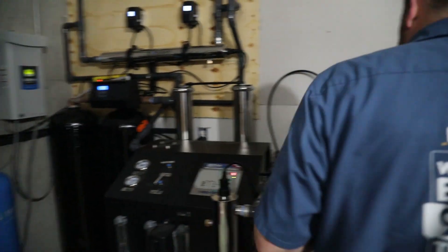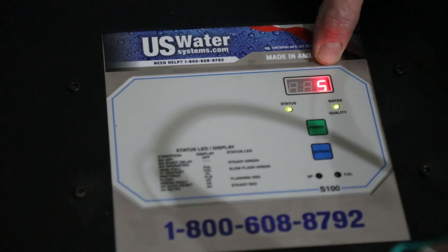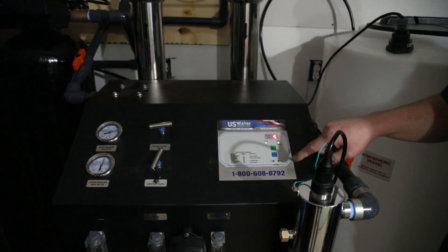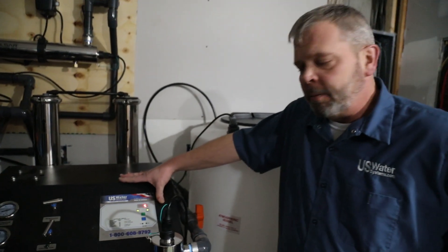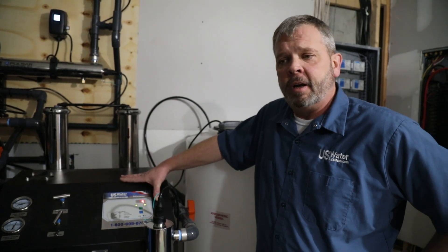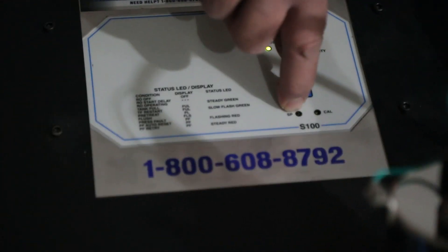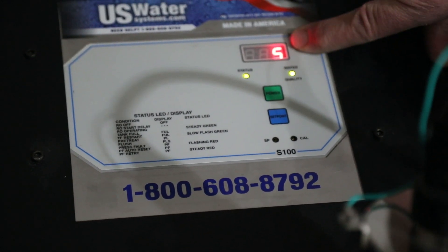Now we're actually putting clean water into the storage tank. You can look at the screen here — we went from like 494 TDS down to high rejection, so we're cleaning really well at this point and the water quality is good. You have the ability to change where you want the water quality light to turn on. We put it from the factory at 100, because depending on how bad your water is, 100 may be the best that you can get. Anything over 100, we would probably need some additional treatment. You have the ability to change that wherever you want — there's a little screw labeled SP, and you can change the set point by pushing the button and then screwing it one way or the other.